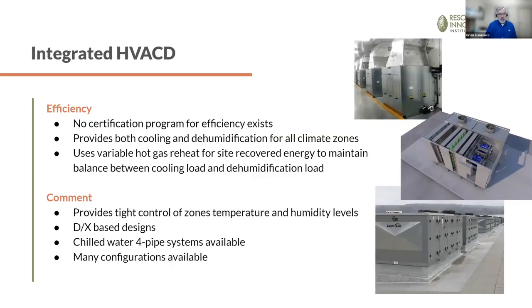And then we have integrated HVAC-D. Again, no certification program exists for this. It provides cooling and dehumidification, all climate zones. Some of these pieces of equipment actually operate up in Canada where it's minus 40 degrees. They use the heat of rejection from the compressors for the free energy to reheat air once it's dehumidified. And they provide really tight temperature and humidity control. So really tight control of that VPD if you have the control system worked out.